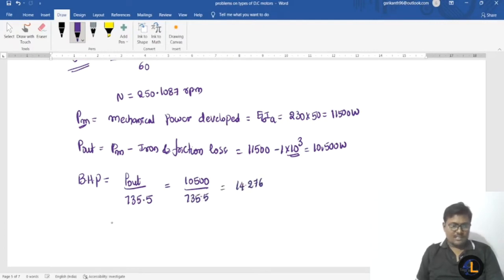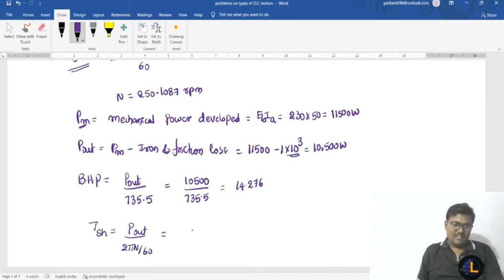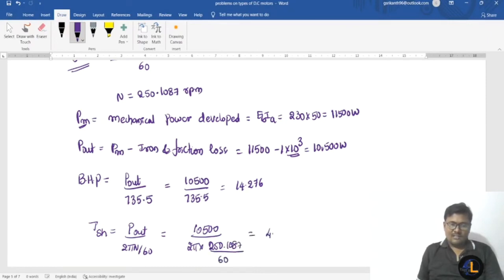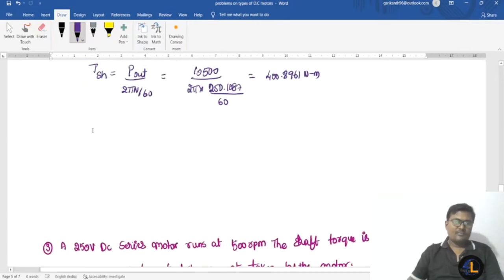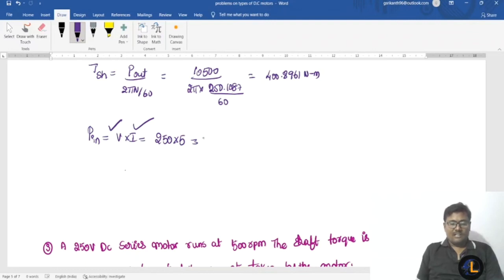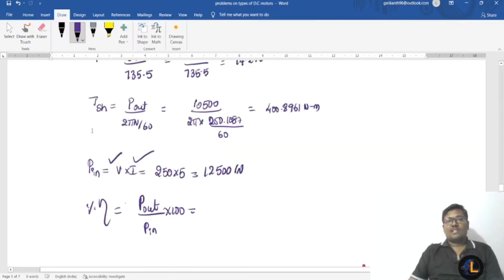BHP = power output divided by 735.5 = 10,500/735.5 = 14.276 BHP. Shaft torque = power output divided by (2πN/60) = 10,500 divided by (2π × 250.1087/60) = 400.896 newton meters. Power input = V × IL = 250 × 50 = 12,500 watts. Efficiency = output power/input power × 100 = 10,500/12,500 × 100 = 84 percent.